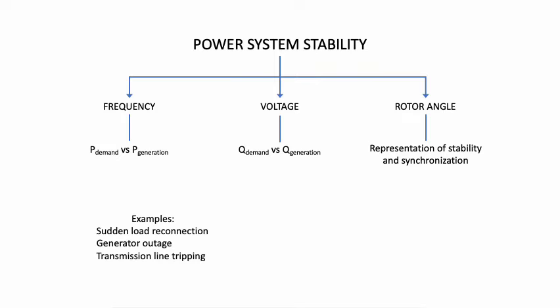When the system is subjected to an abnormal condition, such as sudden load reconnection, generator outage, or transmission line tripping, the subsequent instabilities must quickly be addressed. When they're not addressed, the system could lead to cascading events, which in turn most likely would lead to a blackout.